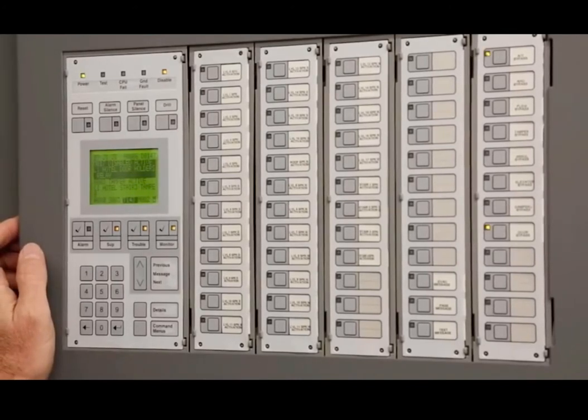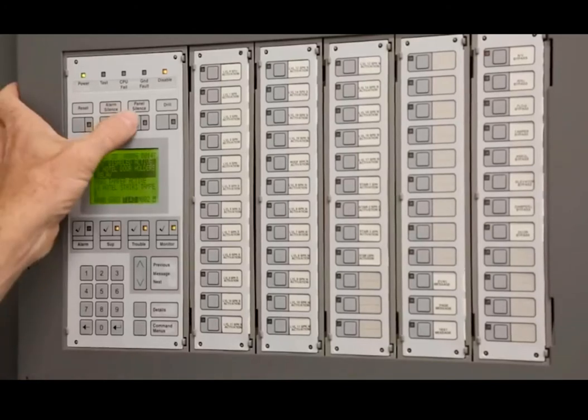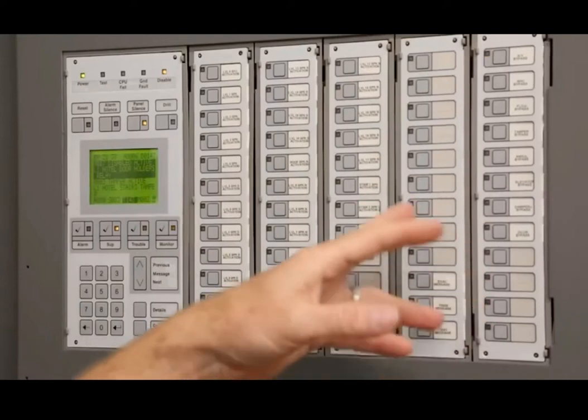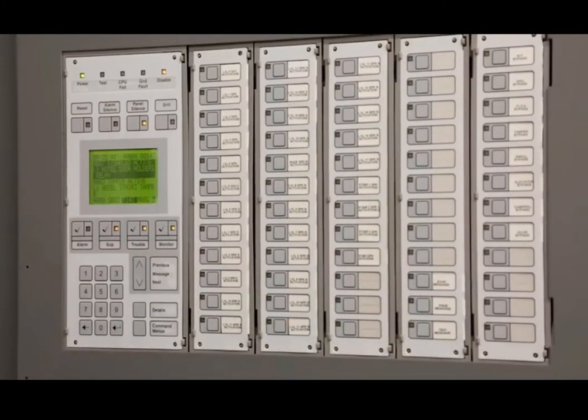So it's a good point to, if you're doing any kind of work around there and you're worried about the system going off, you could have your AV bypassed, you could have your doors bypassed, air handlers, and if you did set it off, you'd still see the alarm come in. It just wouldn't notify anybody. So the bypasses are good for that.